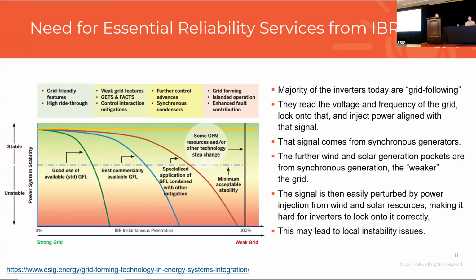So as wind and solar produce power, they disturb that voltage signal for themselves, making it more difficult for them to lock onto it correctly during system disturbances, which can lead to instability issues. So what you can see on this chart is a schematic progression of grids getting from stronger, traditionally powered by synchronous machines, to grids getting weaker, powered by traditional inverter-based resources.